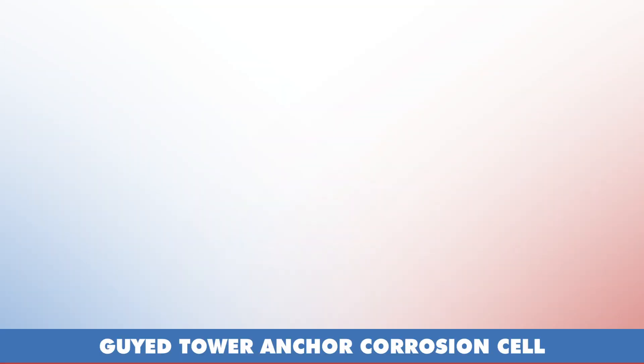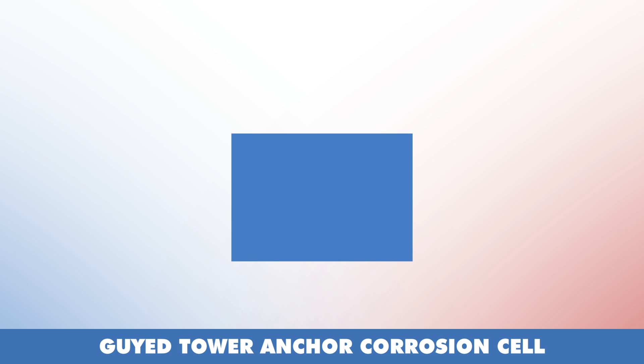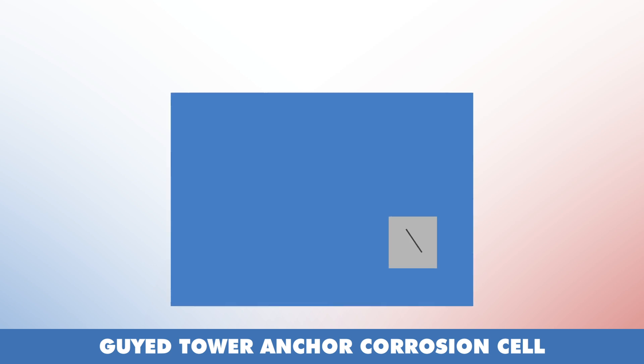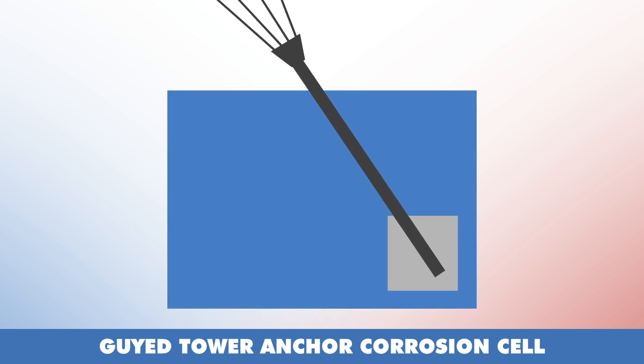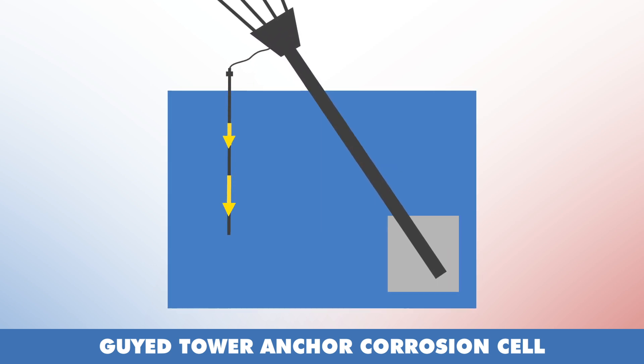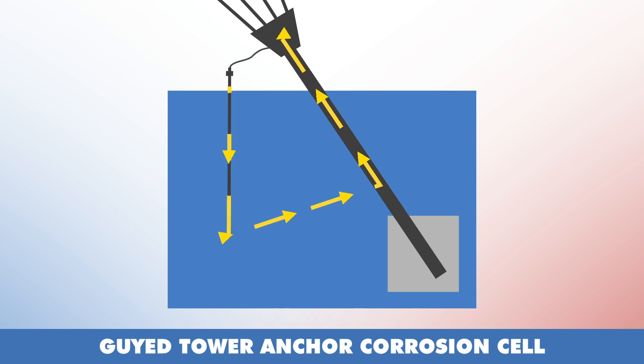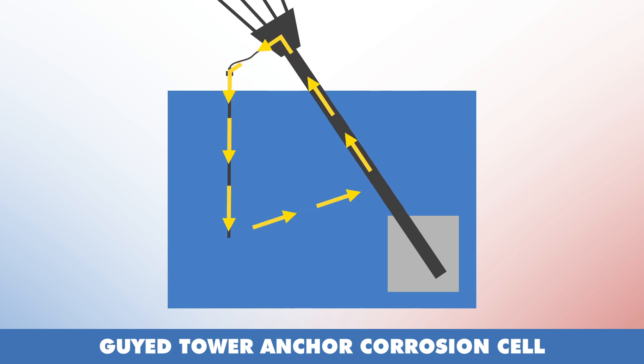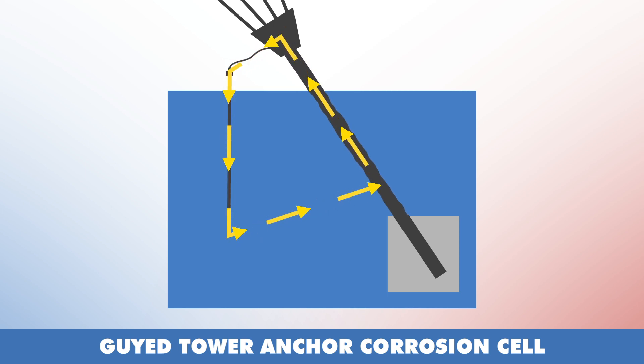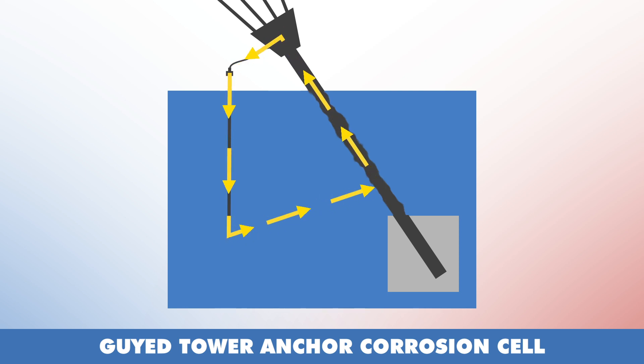Unfortunately, a guyed tower anchor is a great example of a corrosion cell. The steel anchor shaft is the anode, and the copper grounding is the cathode. The anchor shaft is electrically connected to the grounding. The anchor and grounding are buried in the soil, which acts as the electrolyte.